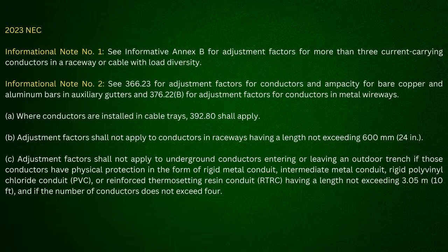Yeah, and that whole cable tray, I'm just not trying to interrupt, just to interject, we ran into this where we run 400 amp parallel conductors to stuff, and we'll run it in cable tray, but we'll have a spacing, and then we'll zip tie those in triangles, and then we'll have a minimum spacing that they give us, but we're not having to derate. No.